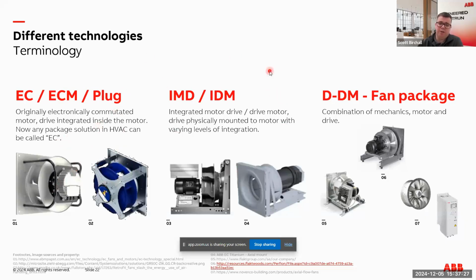You've also got the IMD, the integrated motor drive. This is like a small skid type assembly where the drive is generally mounted to the motor. The big difference compared to the ECM is you can generally specify what type of motor you'd like on this skid, so you've got more flexibility in terms of the type of motor.